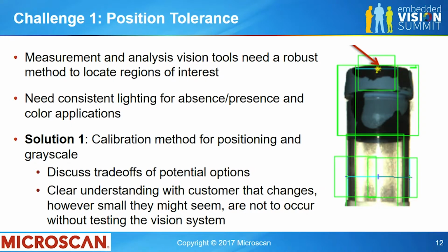Another thing that I mentioned here, and it's sort of a recurring theme, is that they need to understand that any changes, no matter what it is, need to be tested, retested. In one case, we have retroreflective material behind the imaging plane, and the supply chain went out to get a lower cost retroreflective material. Unfortunately, it didn't have the same properties, so our imaging started to look differently during validation testing, and it took us a really long time to figure out what was causing it because no one knew that that material had changed for a while.